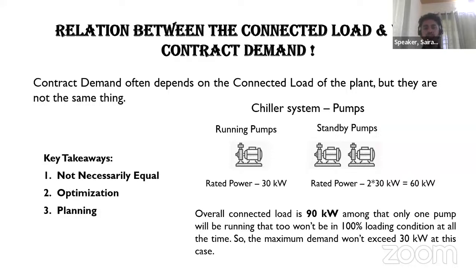So this clearly explains that the contract demand and connected load are different, but they are related. Even if the running pump is operating at 30 kilowatt, it won't be at 100% loading all the time. So the maximum demand can even come under 30 kilowatt. We have to plan accordingly, keeping the connected load in mind, so that the contract demand is placed at a correct amount.